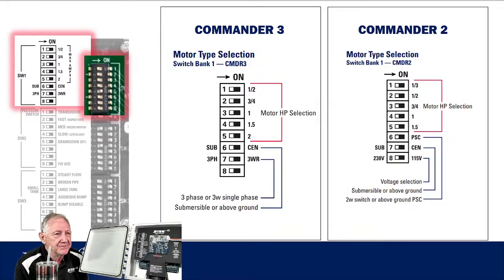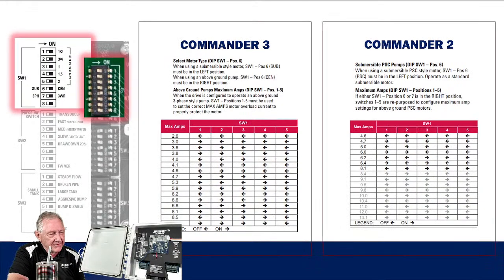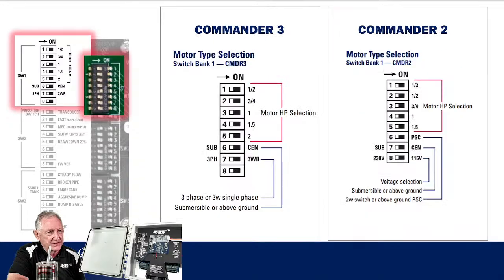And so with that 2-wire, you come down to position number 8. There's your choice between a 230 volt or 115 volt. But the 2-wires are always going to be run on single phase applications. So you've got your voltage selections there. Very easy to set up what kind of pump you're putting in. I'm going to go back here just one slide.